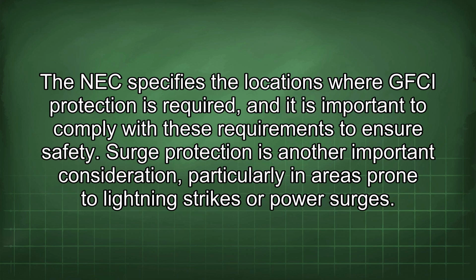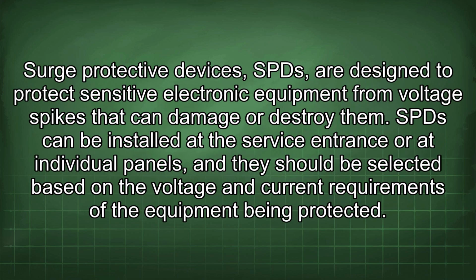Surge protection is another important consideration, particularly in areas prone to lightning strikes or power surges. Surge protective devices, SPDs, are designed to protect sensitive electronic equipment from voltage spikes that can damage or destroy them. SPDs can be installed at the service entrance or at individual panels, and they should be selected based on the voltage and current requirements of the equipment being protected.